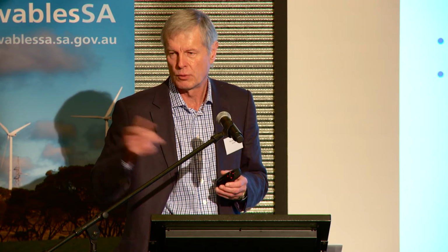You've got to do a certain amount of gas cleanup, but you don't need to do very much for quite a few of the uses of the gas. Typically you're going to get 55 to 75% methane, which is pretty good and means that you can burn the gas directly, though that is not a very efficient way of using the energy in the gas. Far better probably to use a spark ignition gas engine. You can import one from China, as we heard this morning, or there are lots of other suppliers. It's a very well established technology.